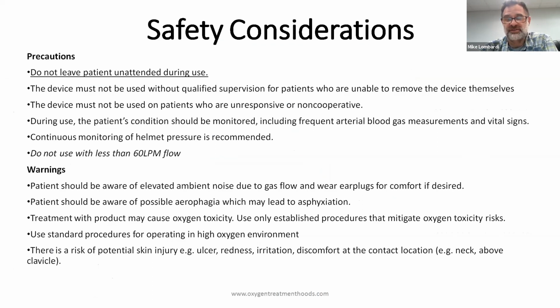Part of that is because of their condition. The other part of it is because these devices are an enclosed space, and if there were failure of the gas supply equipment, there's always risk of suffocation. So the device should not be used without qualified supervision. The device should certainly not be used on patients who are unresponsive or non-cooperative, and during use, the patient should be monitored, including frequent blood gas measurements. We should always monitor the helmet's pressure. That can be done by including a manometer in the patient circuit.